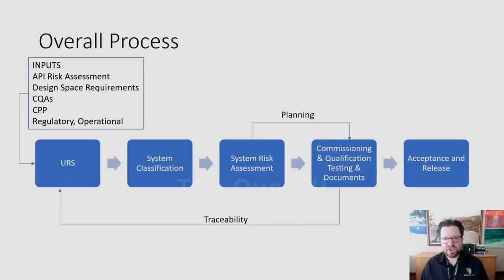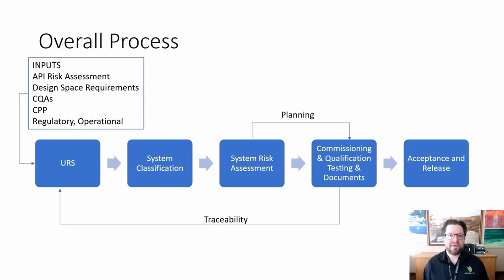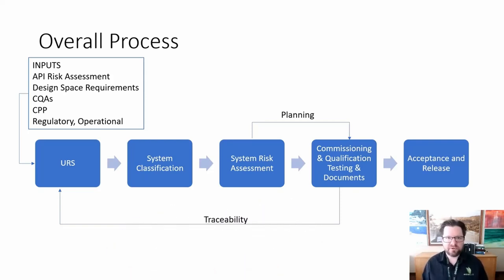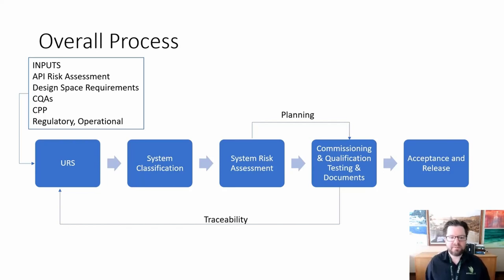So this is the process you typically would follow for selecting equipment, commissioning the equipment, and qualifying the equipment. It really starts off with the URS, which is called the User Requirement Specification. Sometimes your vendor can help you with templates for these — like Xtrek Lab, and we do. You're going to have to add in your own items related to risk assessment, your own critical process parameters, and your own critical quality attributes that will affect the URS.